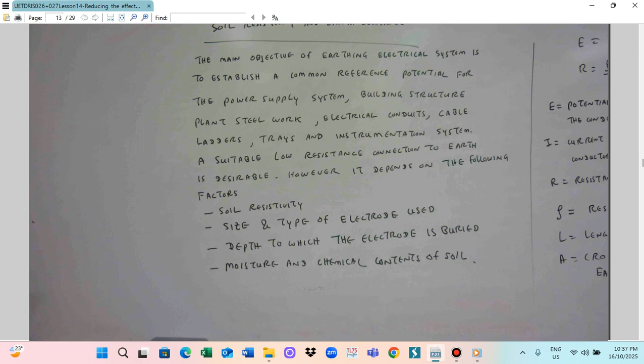So we want low earth resistance. Low earth resistance is desirable, but it depends on the following factors. We cannot always get low earth resistance, especially if the soil resistivity is too high. Also the size and type of electrode used influence the earth resistance, as does the depth of burial of the electrode into the ground. And also the moisture and chemical content. During wet weather earth resistance is low, but during dry weather it is high. The chemical content also influences the earth resistance.